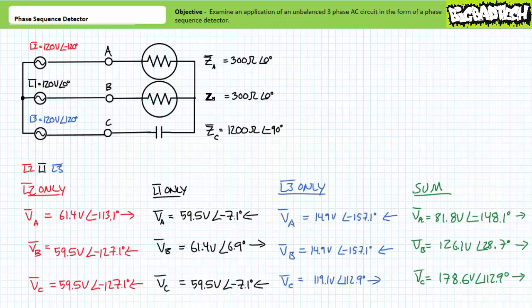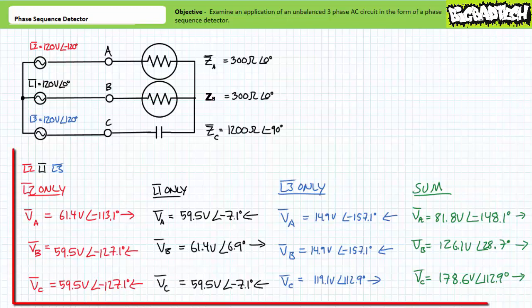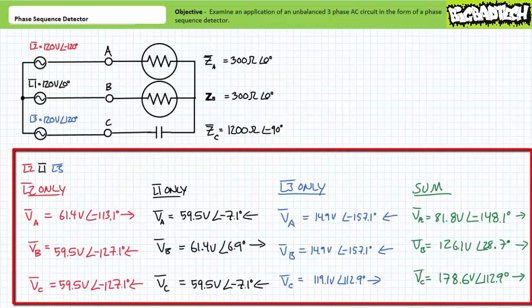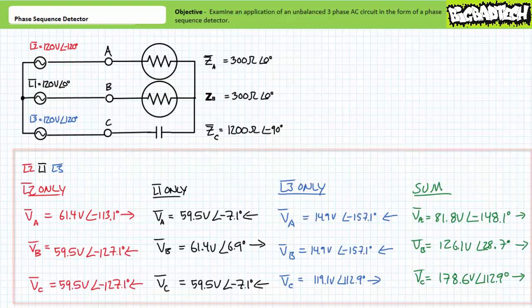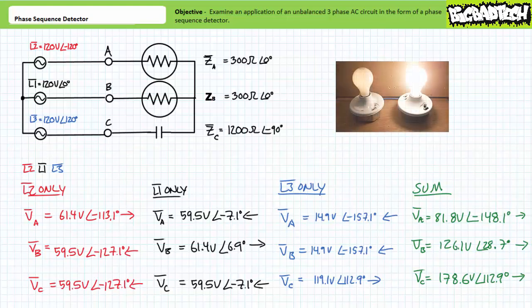Here are the results you'd observe when L2 is landed on terminal A, L1 is landed on terminal B, and L3 is landed on terminal C. As anticipated, given the calculated voltage differentials, it should be obvious that light B would be brighter than light A — a clear indicator that the phase sequence is BAC and not ABC.